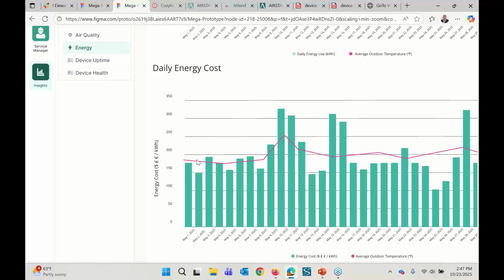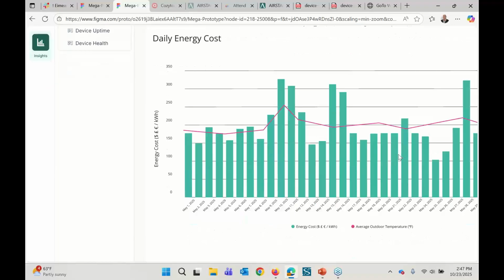Now let's say you have a customer you're trying to convince to go to VRF, and they currently have a building full of rooftop units. AIRSTAGE Cloud is super useful because you can control and monitor rooftop units. You can put rooftop controls on, add CT sensors to the rooftop unit, and start trending energy costs. Then when you replace it with VRF, you move those CT sensors over to the VRF system, and you can show your customer based on graphics how much energy they're saving.